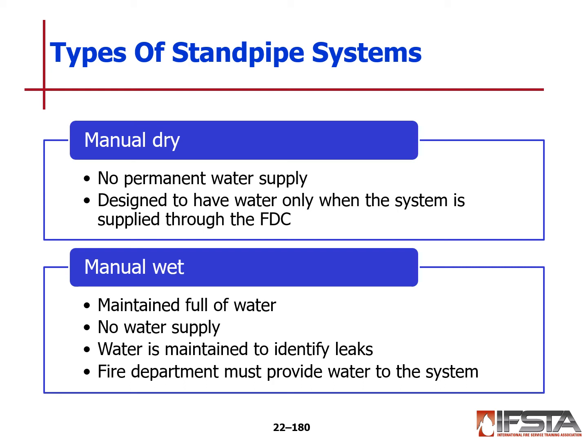Manual dry systems: there's no permanent water supply. These are designed to have water only when the system is supplied through the fire department connection. And then we have manual wet. They're maintained full of water, but with no water supply. Water is maintained to identify any leaks. The fire department must provide water to the system as well.